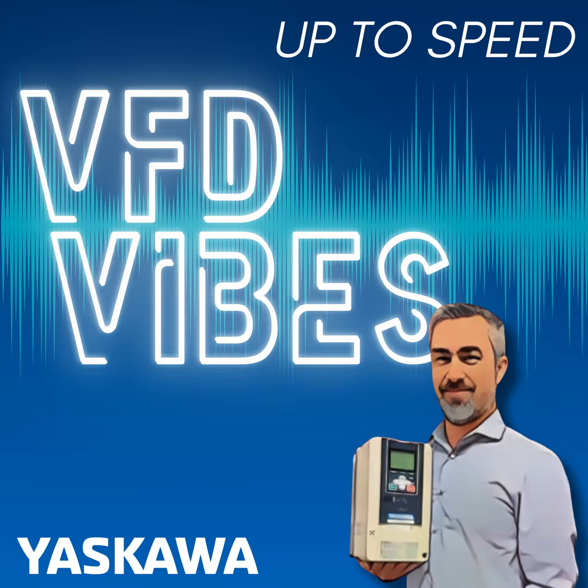Well, the drive uses pulse width modulation to create the voltages that power the motor, but actually the pulse width modulation is designed in such a way that it drives 3 sinusoidal currents into the motor. Yes, there is an equivalent voltage associated with this pulse width modulation, but strictly speaking, it's designed to create sinusoidal currents in the motor. However, a byproduct of this switching at the carrier frequency is a common mode component that drives any capacitance between the motor windings and the motor case, or between the motor leads and whatever's around them, the conduit. And this capacitively coupled current at the carrier frequency has to make its way back into the drive.